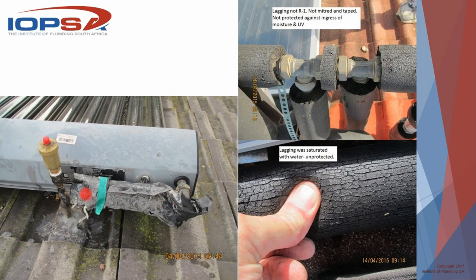Obviously, this isn't acceptable. There's something else there that isn't acceptable either, and that's the waterproofing, or the flashing, if you want to call it that, in air quotes, around that copper pipe: half a tube of silicon. And then this, another example of lagging that has been semi-attempted to be painted, but it's not effective at all. That particular piece of lagging was saturated with water when I got there. It had rained the night before, and it was saturated. It just wasn't doing any good at all.